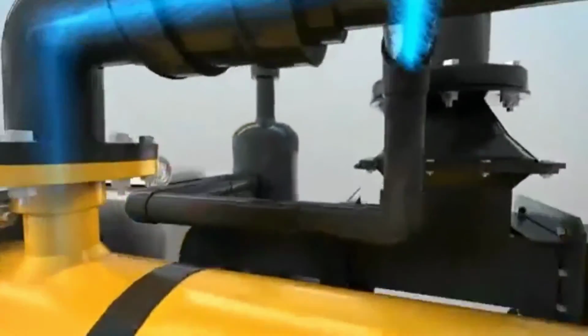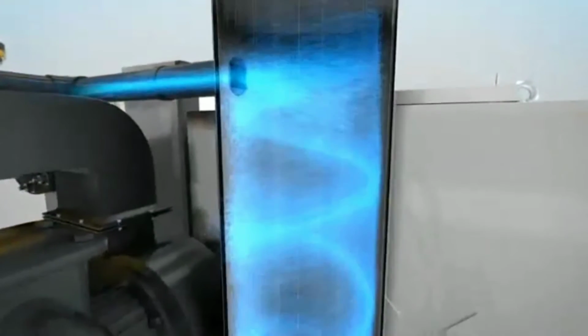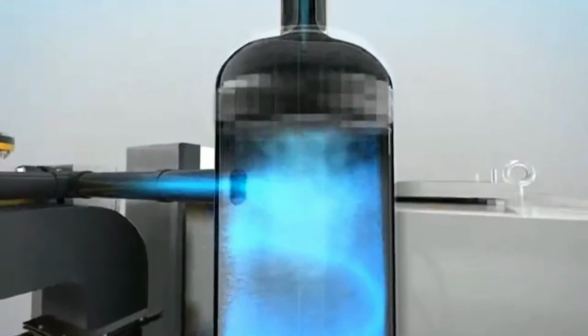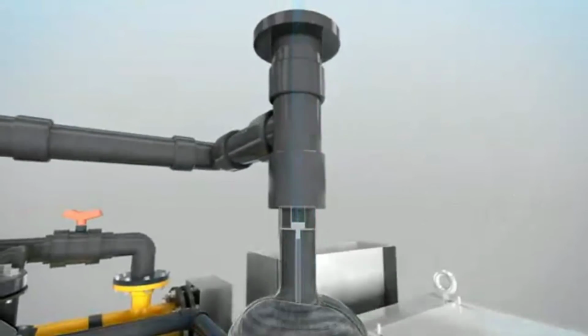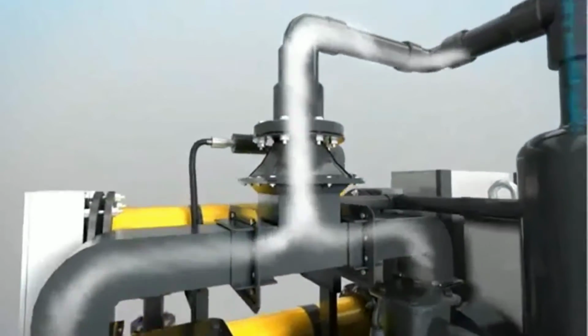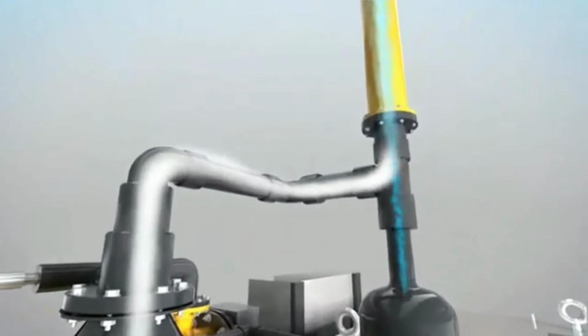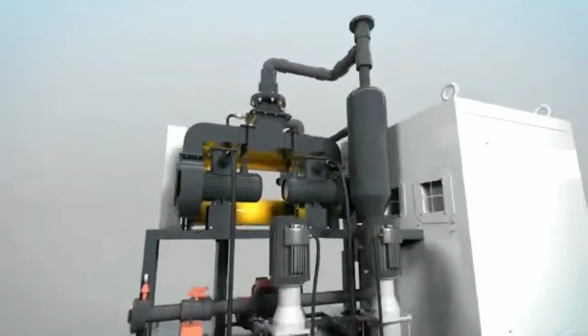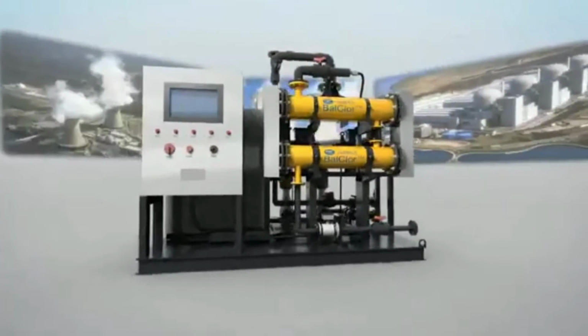Hydrogen bubbles produced during electrolysis go into a cone-type cyclone with electrolyzed seawater to generate a turbulent flow. Hydrogen bubbles are broken into smaller ones during high-speed spinning and then rise with water vapor. After a two-step separation process, vapor becomes fluid and flows back while hydrogen gas is diluted by two blowers to a safe concentration and discharged overboard through a degas pipeline. This degas technology has been operating safely in the nuclear industry for more than 20 years, which fully satisfies the safety standards of the nuclear industry.